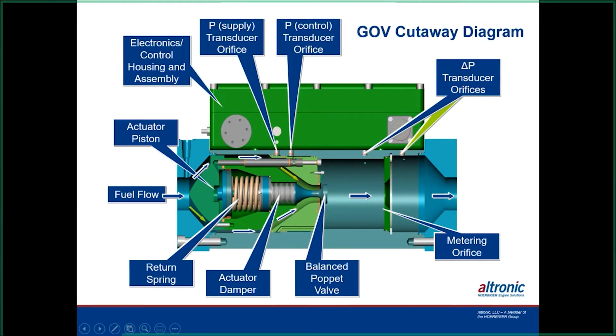Then it has this heavy spring in it. If it happens to lose air pressure or fuel pressure, or if it needs to shut down, the spring will close off the poppet. And then this plate in here with the orifice, this is where we get the fuel flow from. We have two transducers on both sides of that that measure the pressure on both sides and calculate that into a fuel number. So the valve does need maintenance once in a great while, but they've been out there for years running without any problems on them at all.